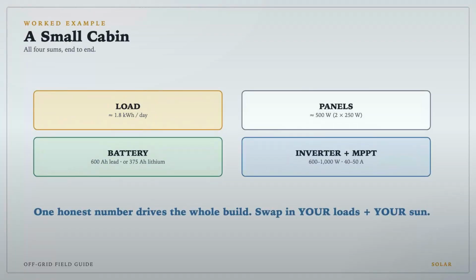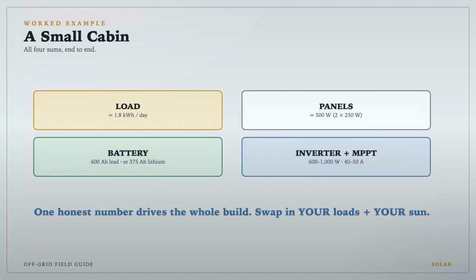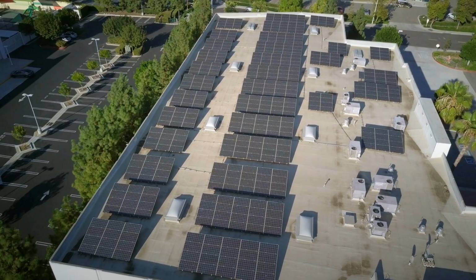A solar system usually tells you what is wrong before it dies. Warm cables mean current is too high, wire is too small, or a connection is loose. A battery that never reaches absorption voltage may be undersized, shaded, misconfigured, too cold, or paired with loads that consume power while charging. A fuse that blows twice is not rude. It is evidence.